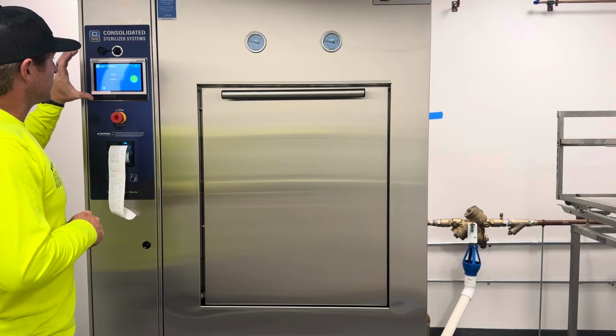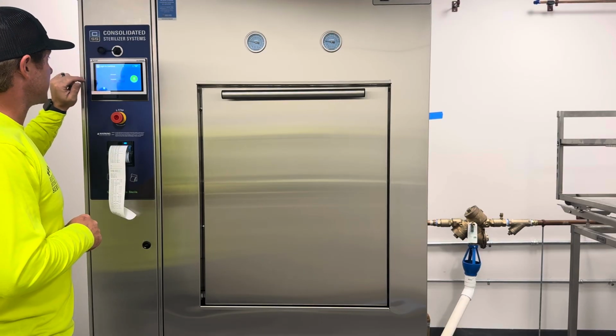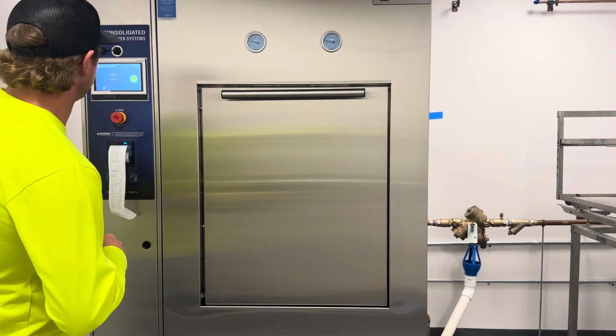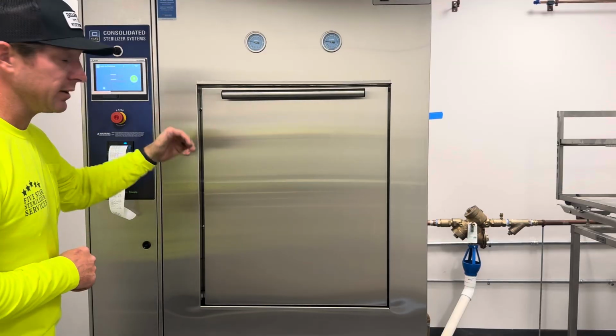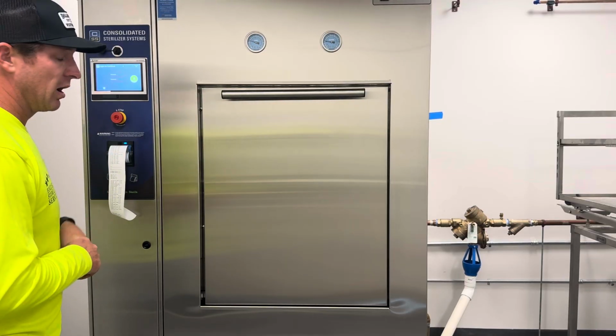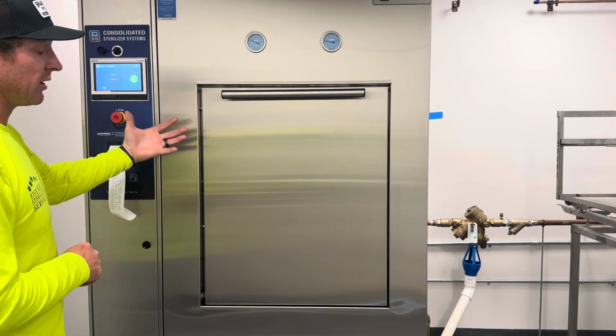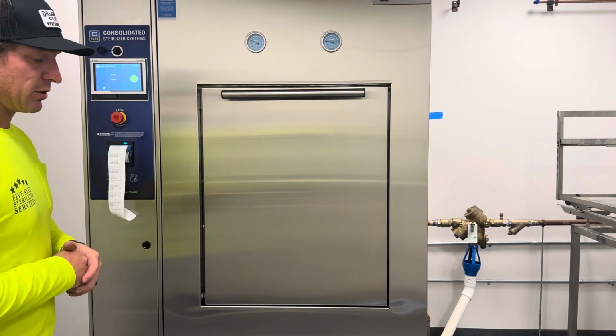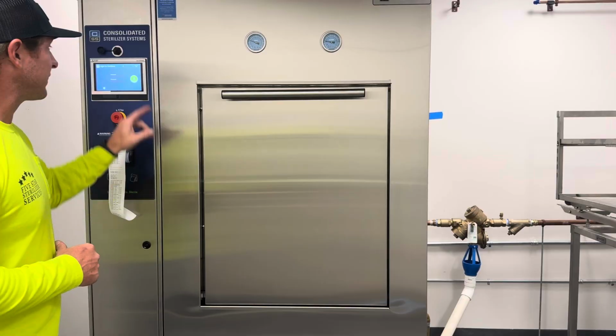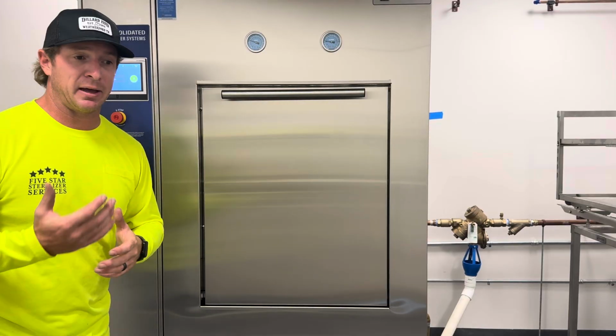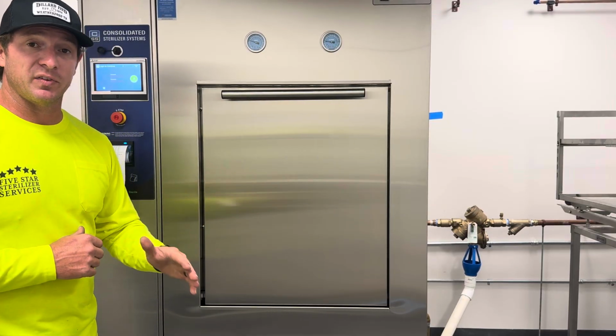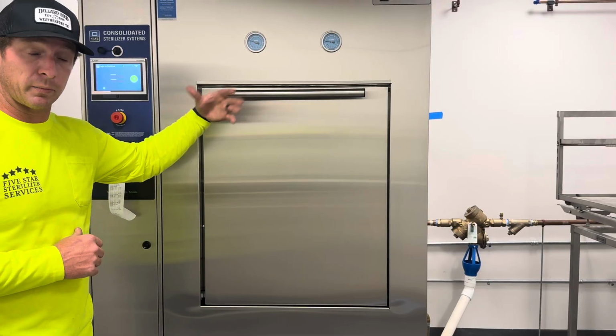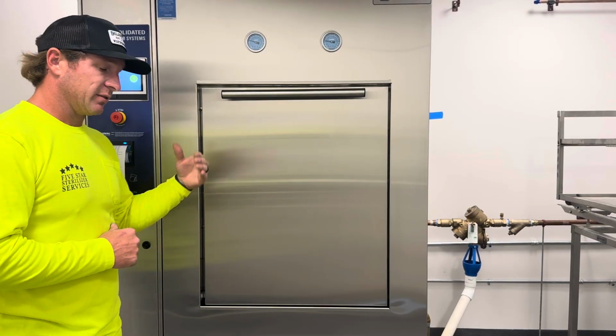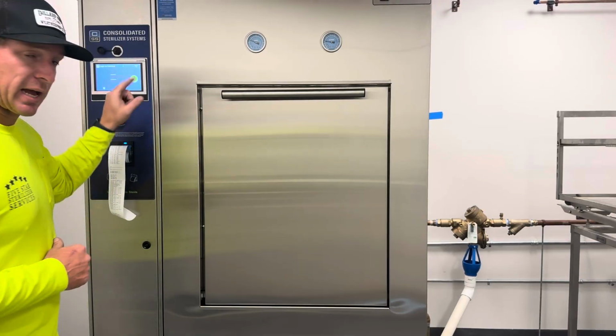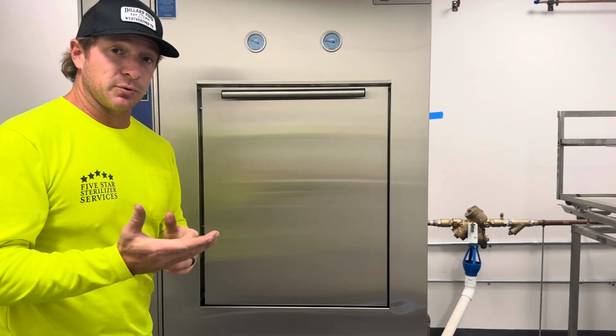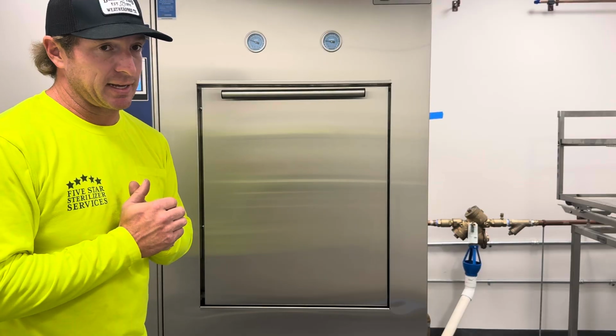Okay, after you wake up the screen and you press anywhere to continue, it's going to prompt you to this screen right here, and then you need to turn the machine on. You need to press jacket on. What that's going to do is turn the jacket on as well as the generator. So on a normal day, if this machine was cold, after you press jacket on, you would need to allow at least 30 to 45 minutes for this machine to warm up and be ready to use. If you come in here and it's cold and you turn the jacket on and try to run the machine immediately, most likely it's going to fail.